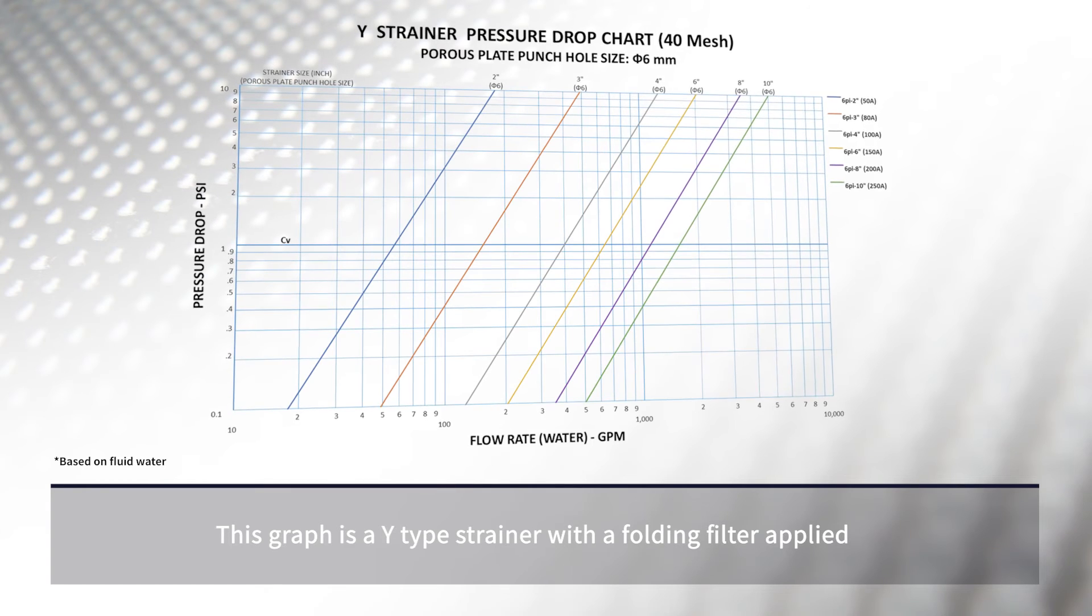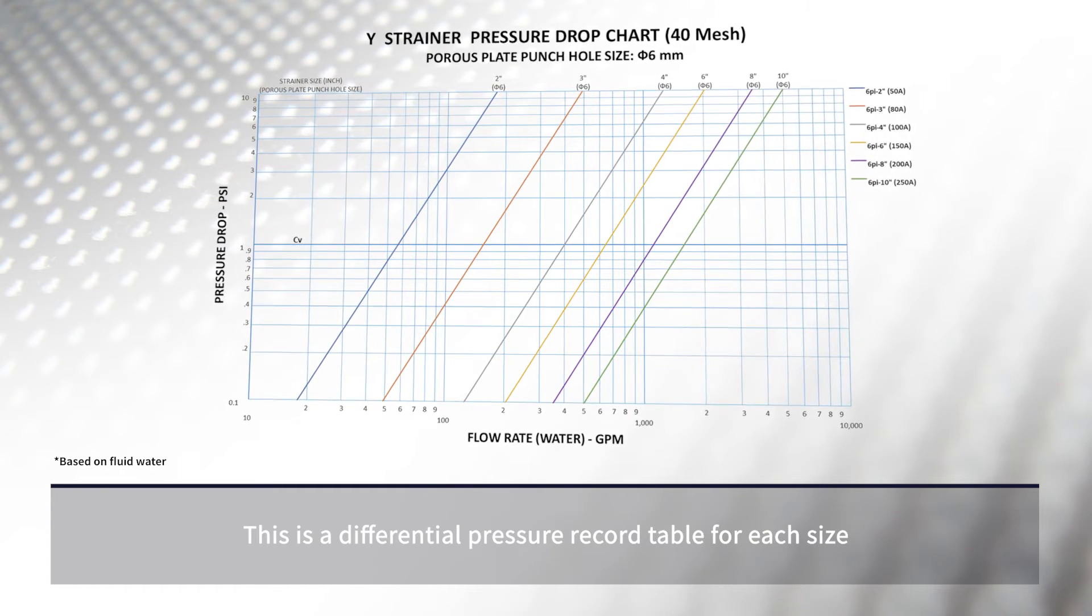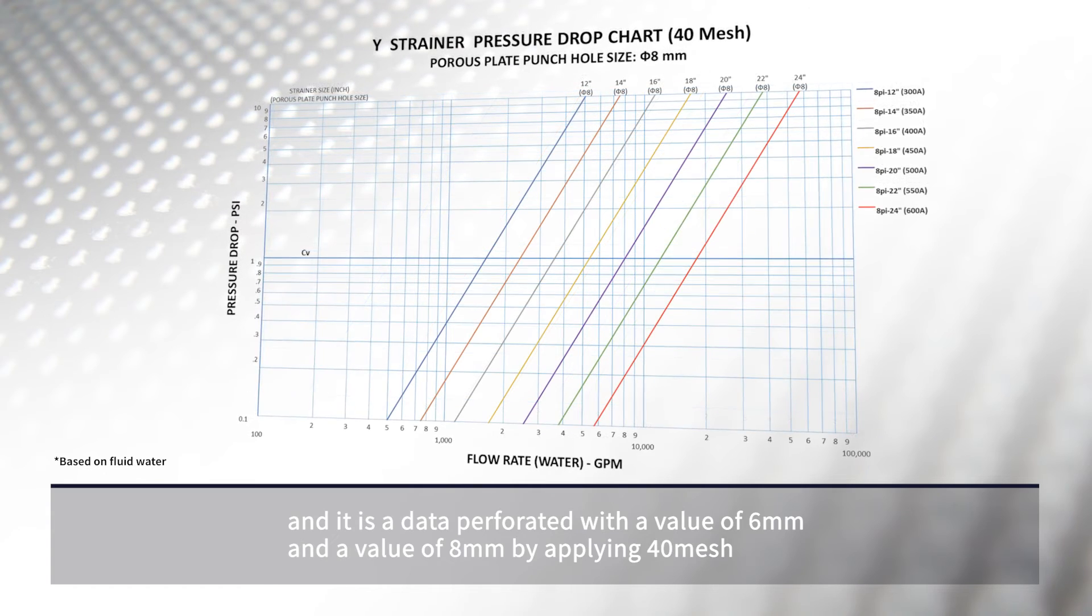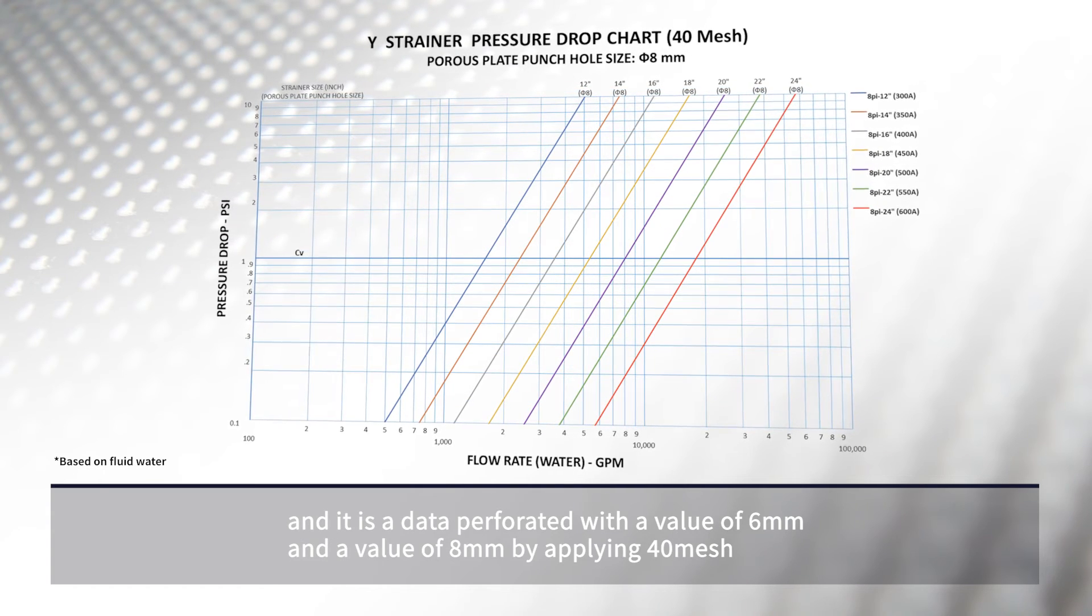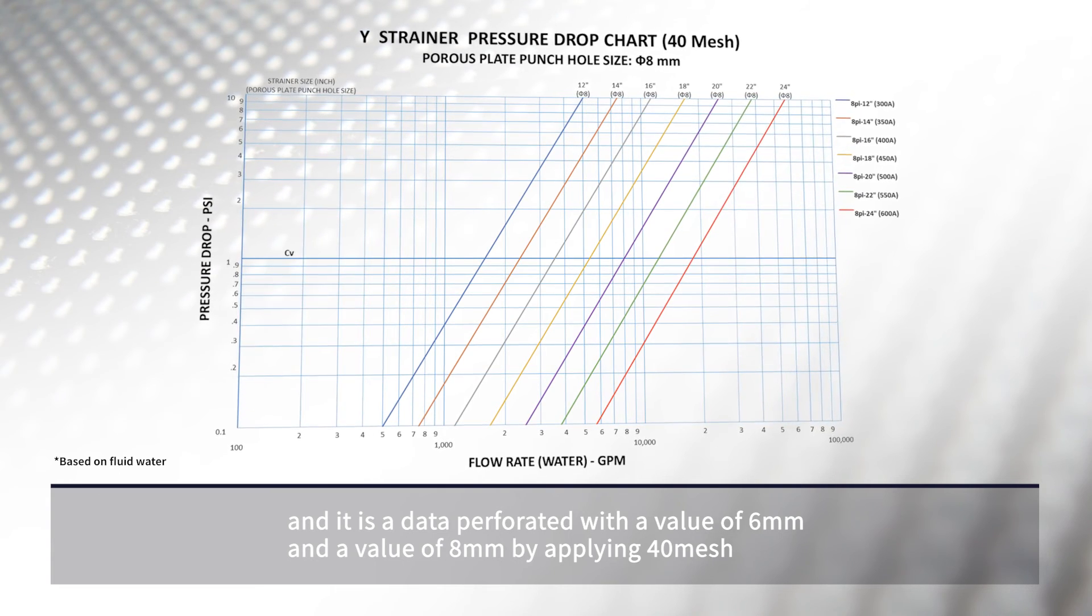This graph is a Y-type strainer with a folding filter applied. This is a differential pressure record table for each size, and it is data perforated with a value of 6 millimeters and a value of 8 millimeters by applying 40 mesh.